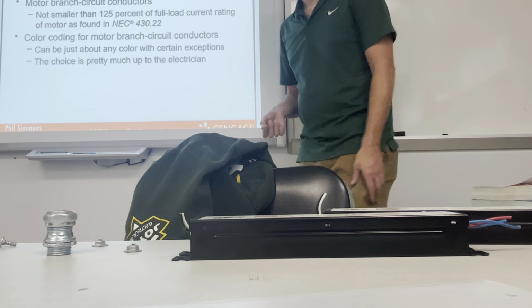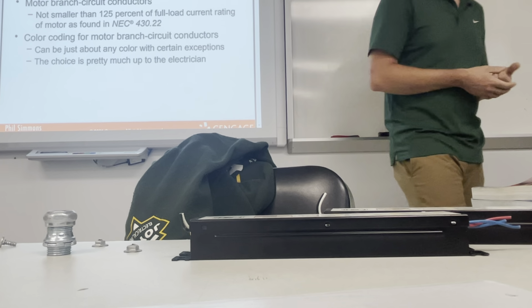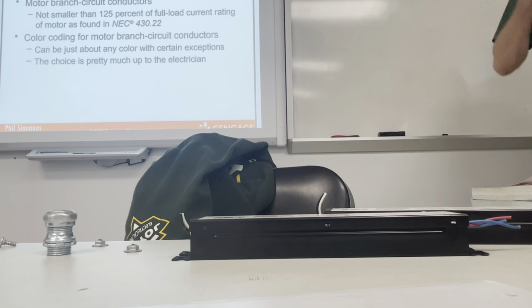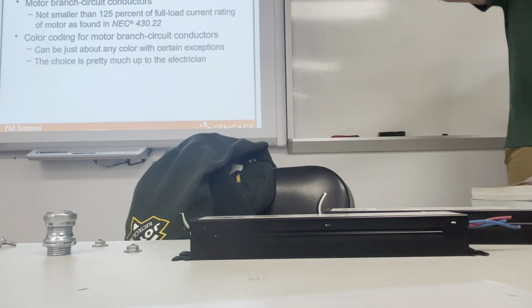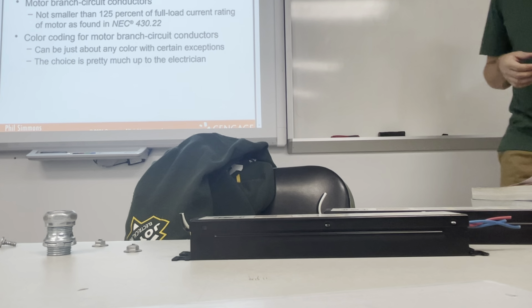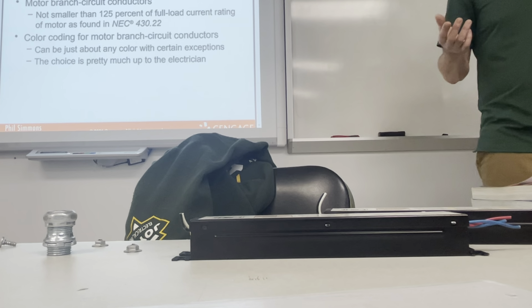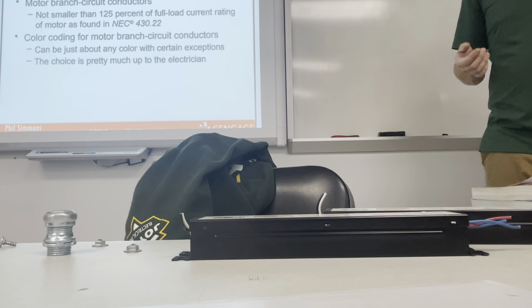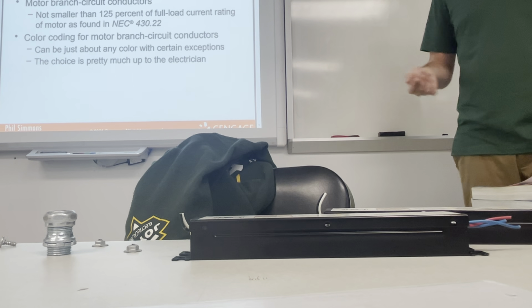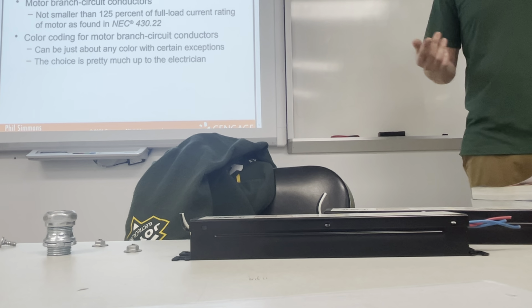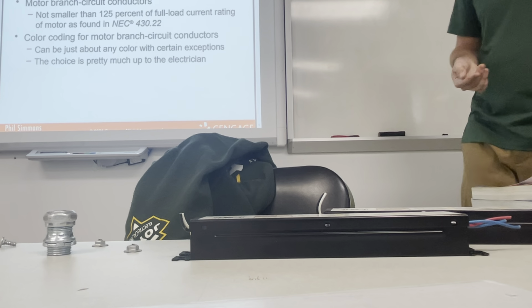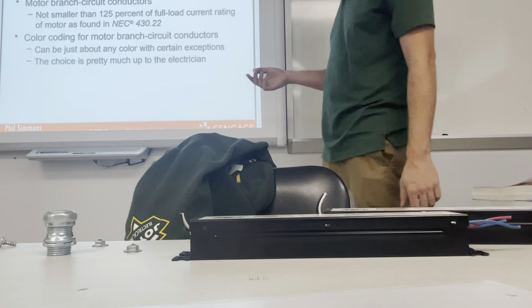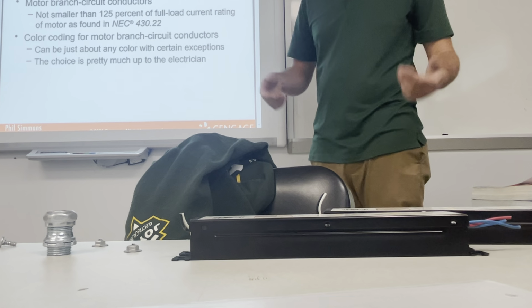But yeah, color coding. When we're in lab, like all the control work, because there's the high side and the low side. There's the main power side, and then there's the control side, which you guys in PLC are really concentrating on, right? See what all your relays can do. Your starts and stops are all in a particular order. That's the easy side. Usually that's all in one color. I usually do red or black. The 3-phase side of it though, there's no harm in having your black, red, and blue, or if it's 480, your brown, orange, and yellow. It's just going to make things a little easier to see, and you can see what legs are what.